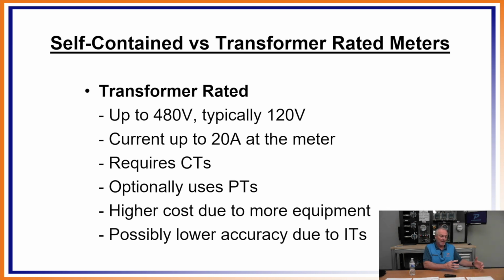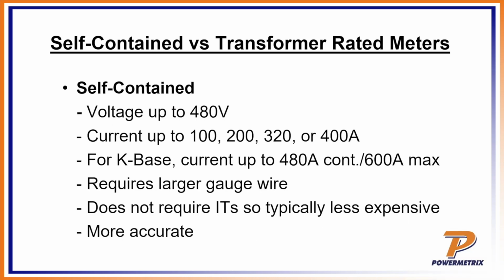So all of them have an accuracy, and they also have a level of inaccuracy. Each one of these levels of inaccuracy that you're adding accumulates, so you tend to have a lower accuracy due to those instrument transformers. So self-contained: you've got voltage up to 480 volts, and the current ratings are 100, 200, 320, or 400 amps. And for a K base, you can have current up to 480, continuous 600 amps max.